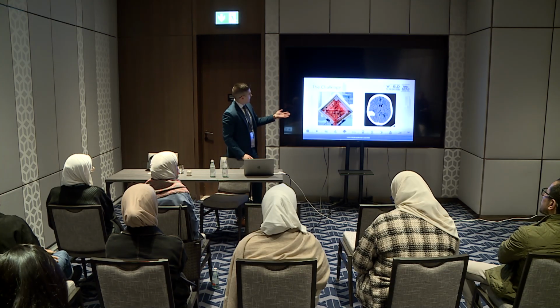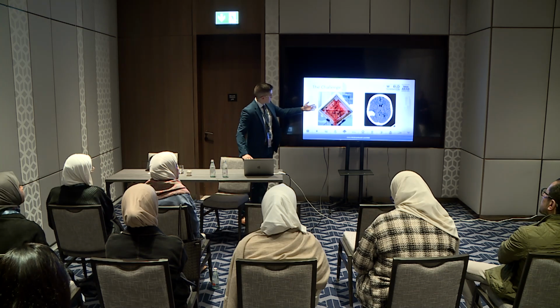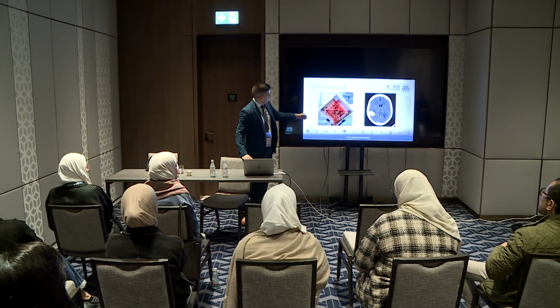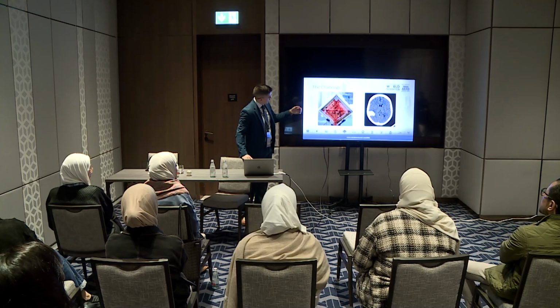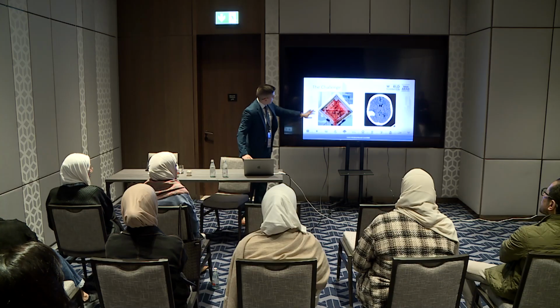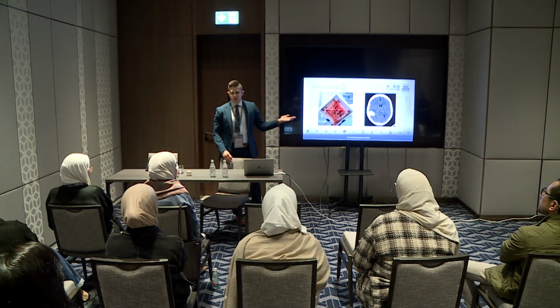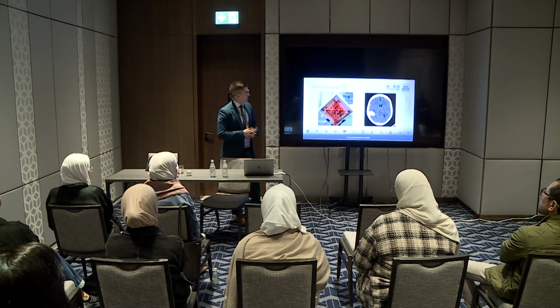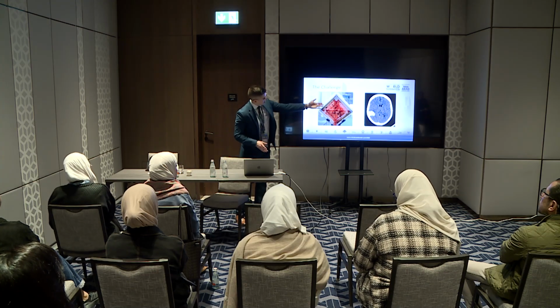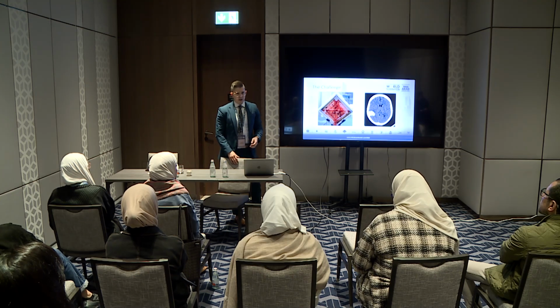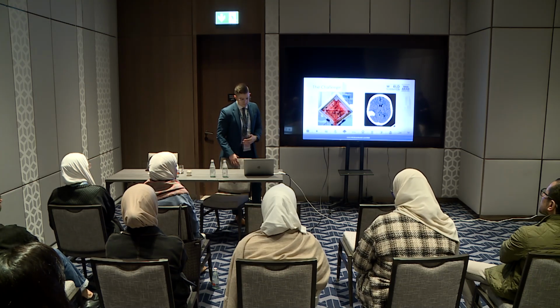And so the ECMO provides a unique challenge. So on one hand, we want to preserve the function of the membrane. So this is, again, a membrane that is no longer being used for support if it's been washed with saline. But you can see all the clot that's in there. And this is not good, because the more clot you deposit into the membrane, the less efficient those fibers are at exchanging gas. And so we want to prevent this, but also we don't want to have catastrophic intracranial events.